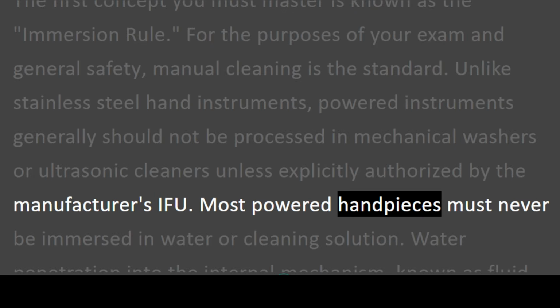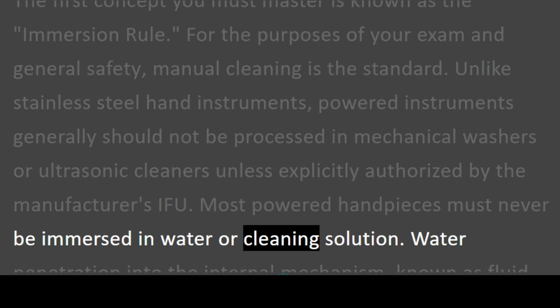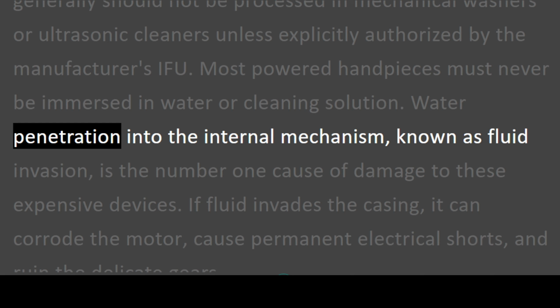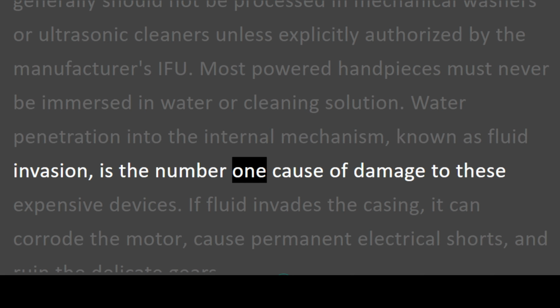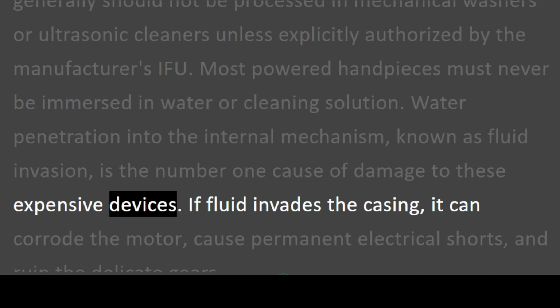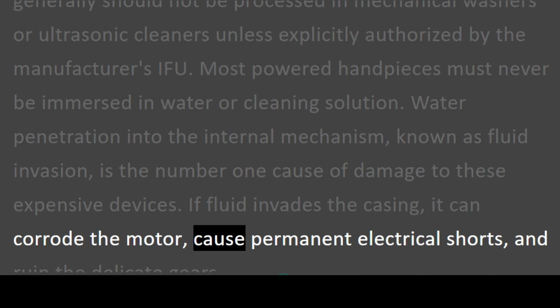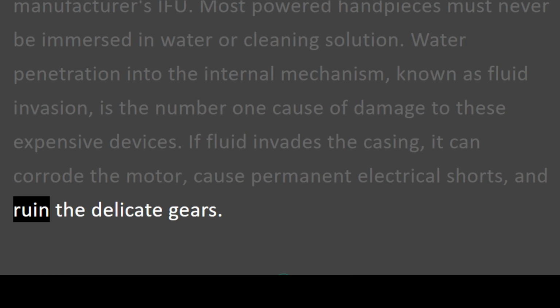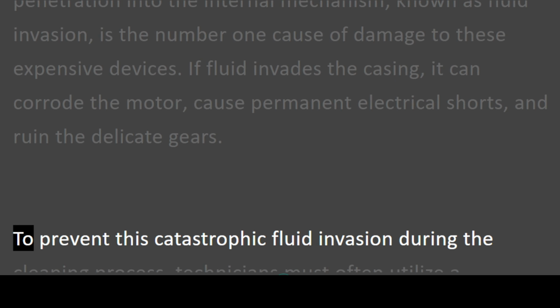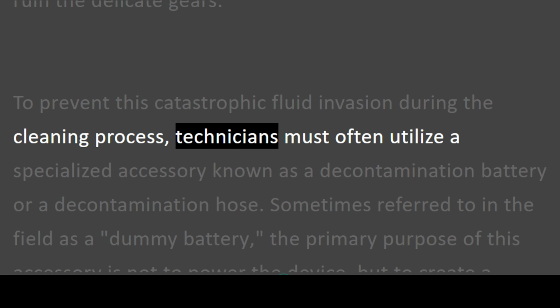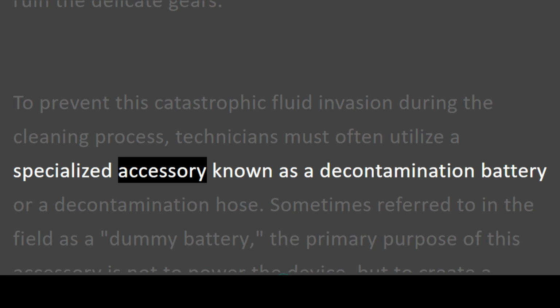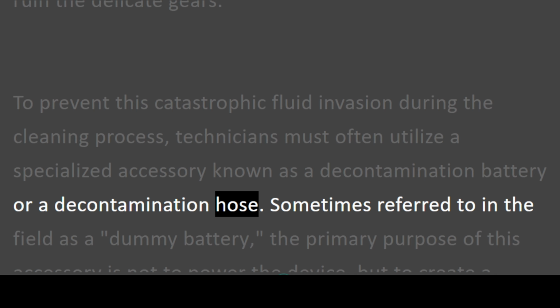Most powered handpieces must never be immersed in water or cleaning solution. Water penetration into the internal mechanism, known as fluid invasion, is the number one cause of damage to these expensive devices. If fluid invades the casing, it can corrode the motor, cause permanent electrical shorts, and ruin the delicate gears. To prevent this catastrophic fluid invasion during the cleaning process, technicians must often utilize a specialized accessory known as a decontamination battery or a decontamination hose.